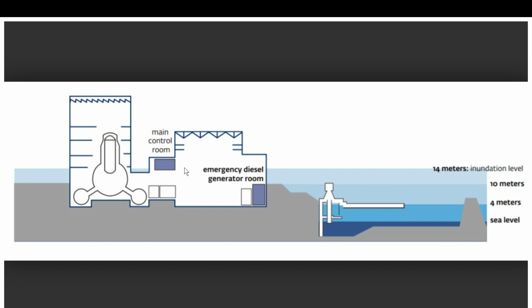So here we have a little mock-up of the reactor and then the emergency diesel generator room. The tide wall was 5.7 meters high, which means that a little water that comes over here can get trapped by this, and then they had pumps to pump it out. They were okay most of the time. The report said, hey, you need to double the height of your seawall pretty much from 5.7 to 10.2 meters, which of course they did not do.